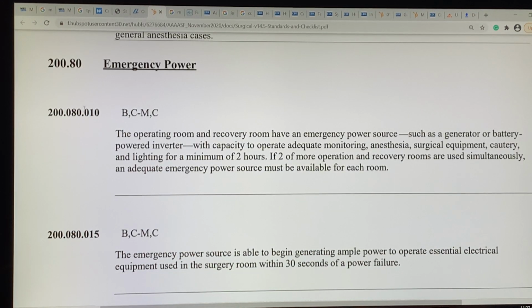Emergency power, 200.80.10: Operating room and recovery room have an emergency power source, such as a generator or battery-powered inverter, with capacity to operate monitoring, anesthesia, surgical equipment, cautery, and lighting for a minimum of 2 hours. If 2 or more operating and recovery rooms are used simultaneously, you have to have one for each room.